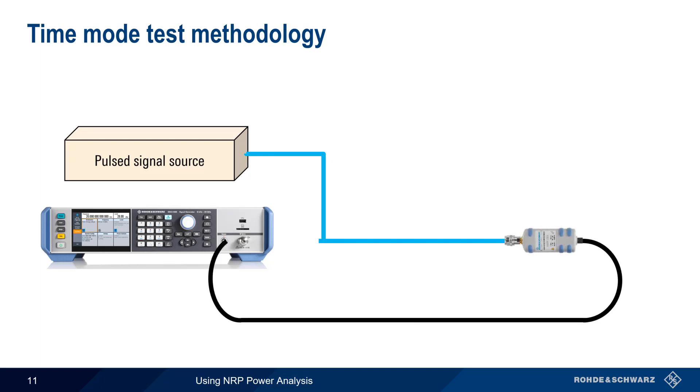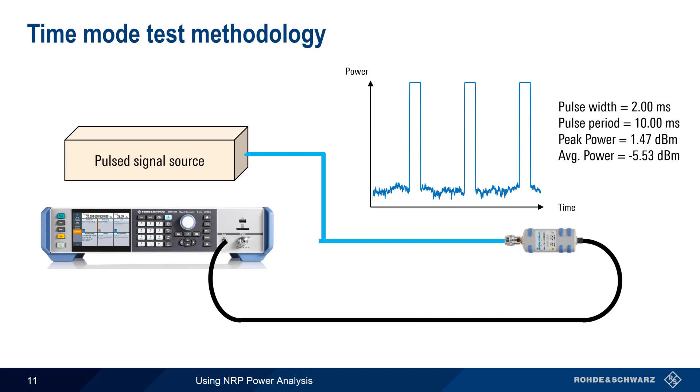Unlike frequency and power mode measurements, in time mode we can measure signals from any source. Signals could be generated by the SMA through some device under test, or the signals could be coming from some external source. In either case, the NRP sensor measures the received signal and displays the results in the time domain, that is, as power versus time. In addition, various pulse parameters can also be automatically displayed and calculated.